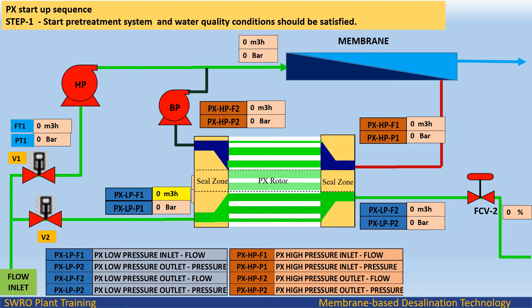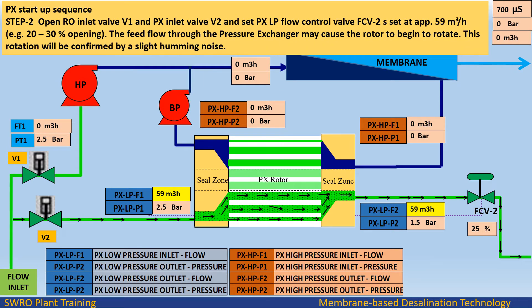PX startup sequence, step 1: start the pre-treatment system and ensure water quality conditions are satisfied. Step 2: open RO inlet valve V1 and PX inlet valve V2, and set PX LP flow control valve FCV2S at 59 cubic meters per hour, with 20–30% valve opening. The feed flow through the pressure exchanger may cause the rotor to begin to rotate, confirmed by a slight humming noise.